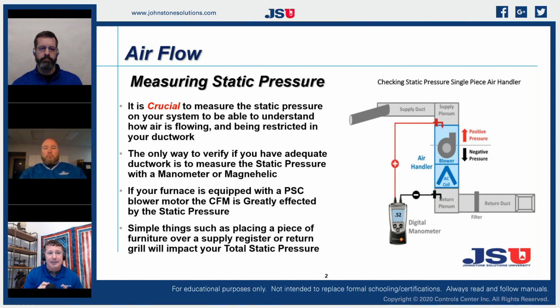So with an air handler, I am only including the things that came from the factory. I haven't seen them in a long time, but I have seen air handlers that came with a hog hair filter installed in them. It's been a long time, it shows a little bit of my age, but we used to have those. Hog hair was a pretty common filter that came from the OEM in the piece of equipment. So if I had an air handler with a factory installed filter, that filter is also included in that pressure versus CFM chart for that blower.